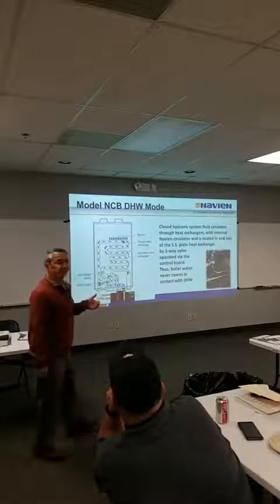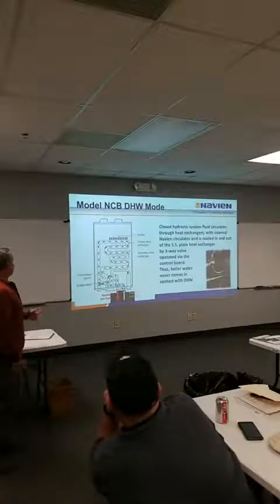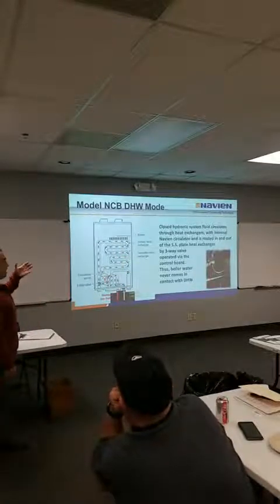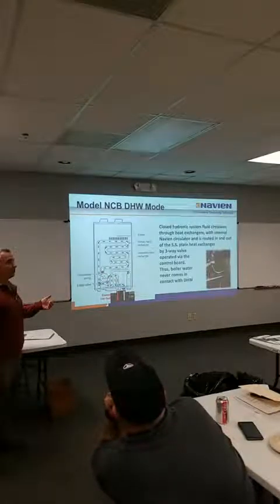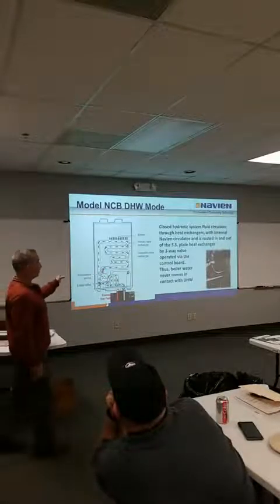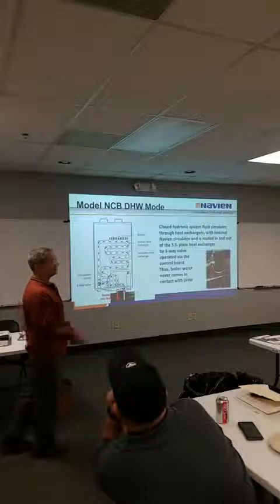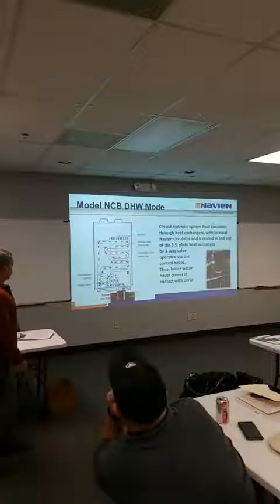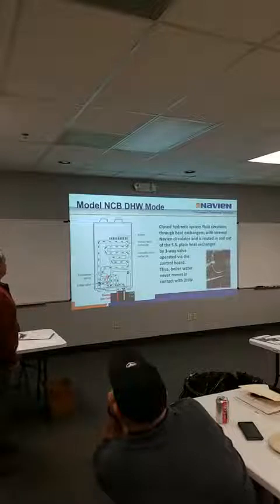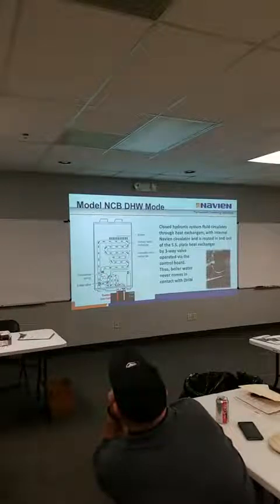The pump's built in? Yes, it's a built-in pump. So you'll see higher temperatures coming out of the boiler when you're in domestic mode, because we have to heat that flat plate heat exchanger and get your domestic up to temp. That's kind of like what I'm doing now. Pretty simple operation, not a whole lot of moving parts. We've been doing it the same way since we came out with combi, I think, in 2010 or 11.